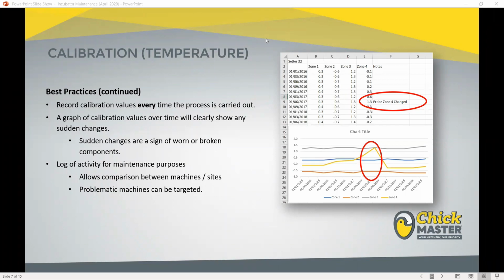But a lot of it comes down to the experience of the individual site, which is why recording these values is so important. Your offset value is impacted massively by, as I mentioned earlier, the resistance of the cable. Now that's impacted by relative humidity, ambient temperature, barometric pressure, and the age of the cables as well. So if you're consistently calibrating your incubators to 1.2 degrees, and that's repeatable, then it's absolutely fine. It's not a problem. If, however, you're consistently calibrating your machines to 0.2 Fahrenheit, and then you've got one incubator that jumps up to 1.2, then that individual incubator is a potential problem.